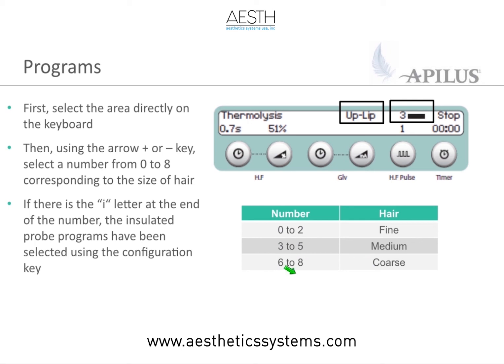Be careful when you go up high with double tapping or triple tapping or however many pulses you think that you need to deliver. Any of these machines, preset or not, can cause a lot of damage if not used properly. So be careful with how much intensity you are delivering in the skin.